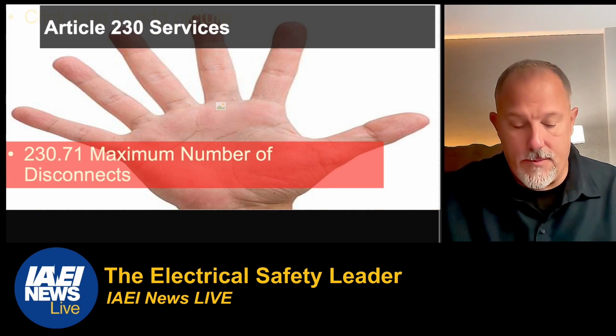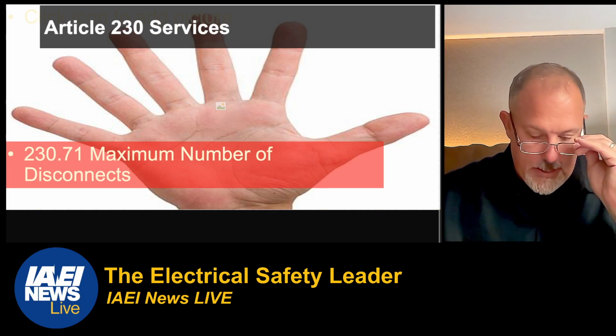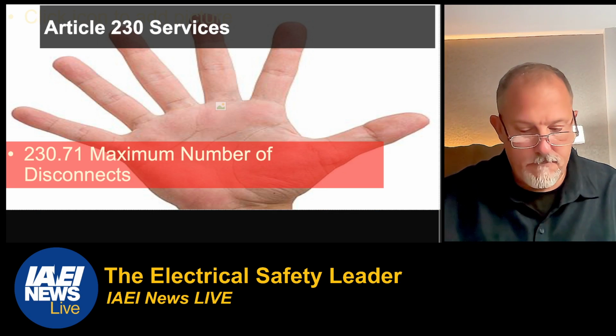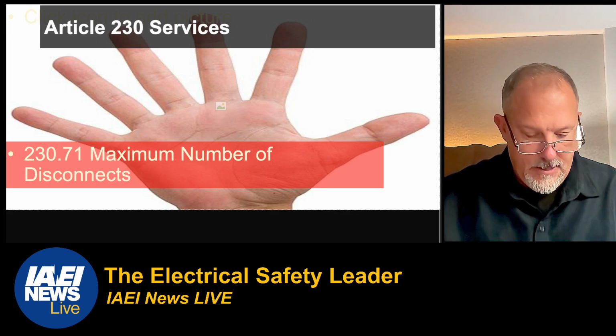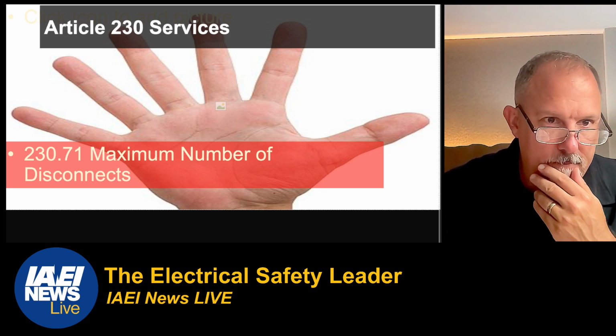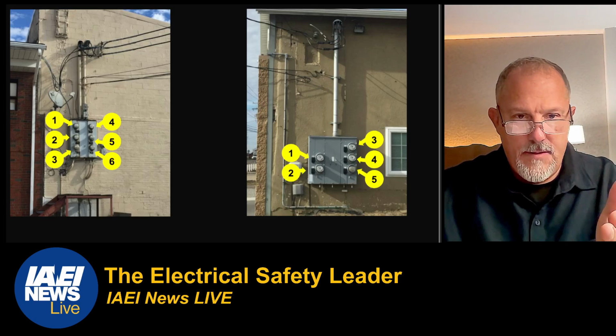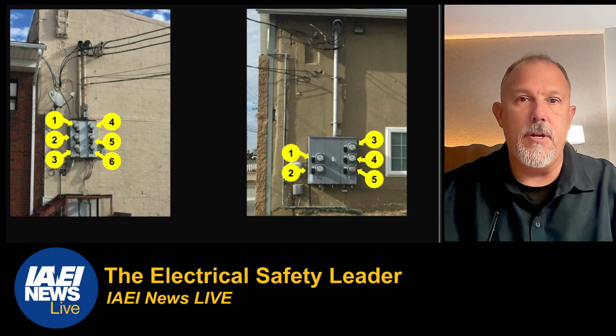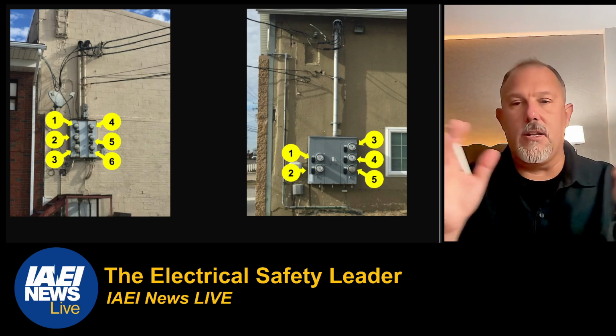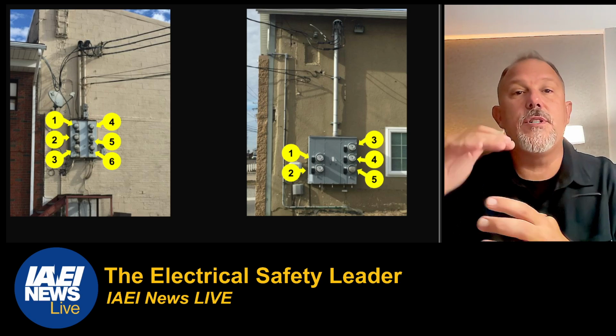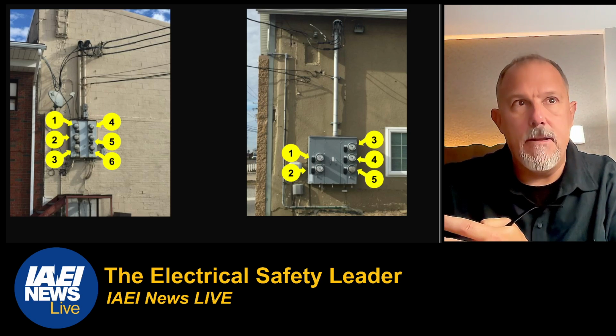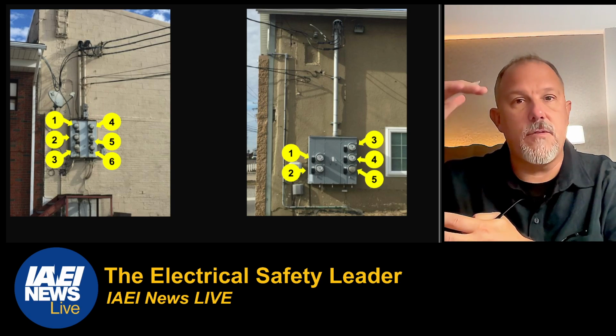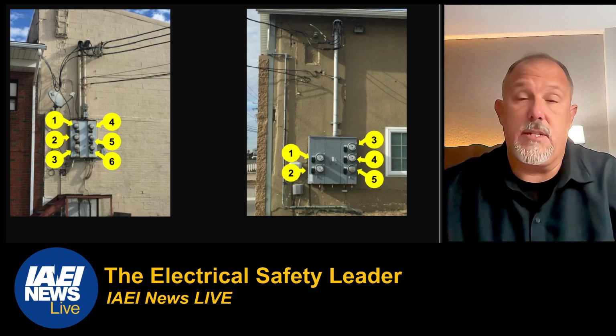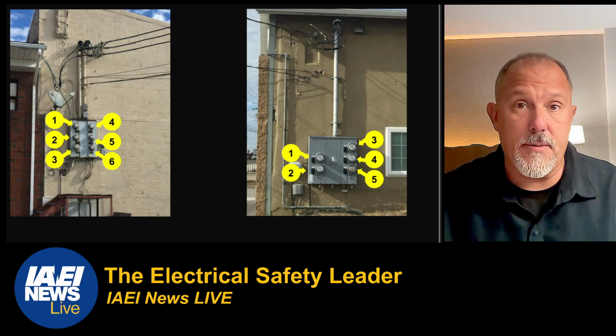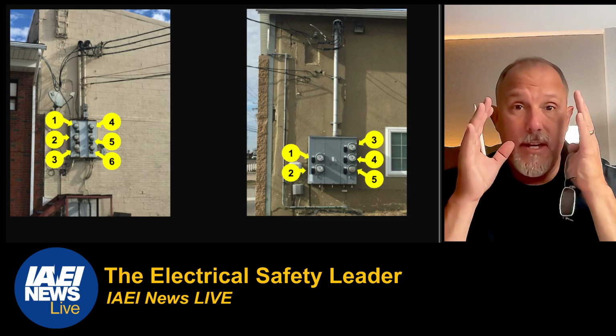All right. So now we're going to get out of AFCIs. 230.71. Now 230.71, I don't know if I have it here. You know that these items, the meter centers, were the problem. So the 2020 code put in this provision. What they were trying to address was, remember, we put the line side barrier requirements in to barrier off the line side service entrance equipment, service overcurrent protective device. And we said, look, panel boards, you can't do 6 disconnects in a panel board anymore, period. You're going to have to put a main breaker in a panel board. Can't have a panel board with 6 disconnects because of that big bus that's in the middle.